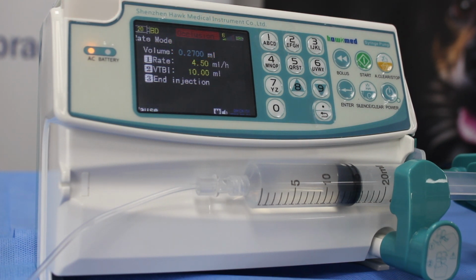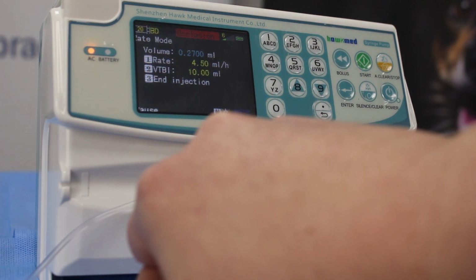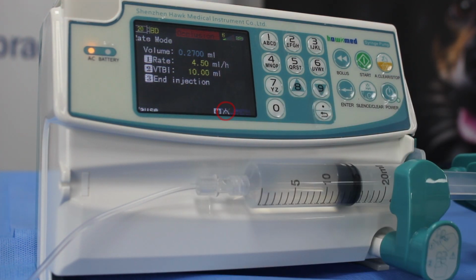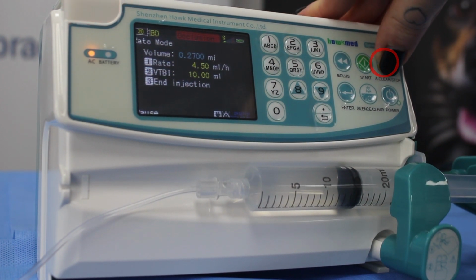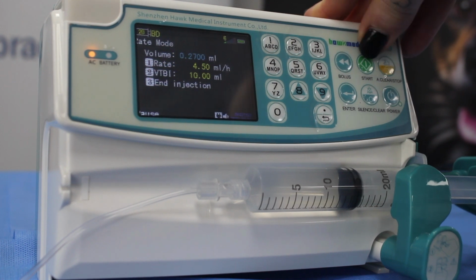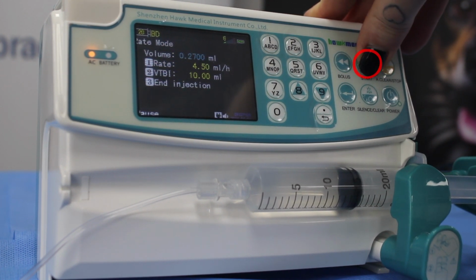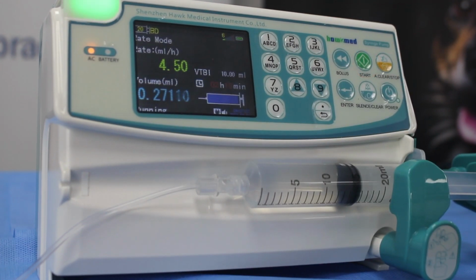We can silence the alarm while we get to work on resolving the occlusion by pressing the silence button. This will show a temporary pause on our alarm at the bottom screen here. Once we've resolved the occlusion issue, we can then clear the alarm with the A.clear, which is alarm clear button. And we can press start again to restart our infusion on our patient.